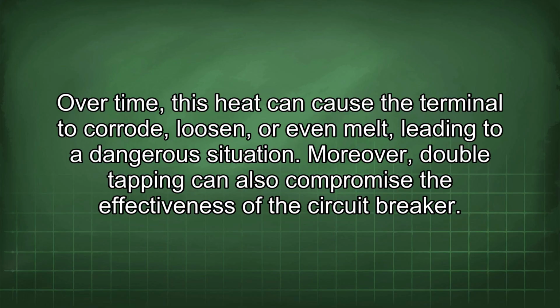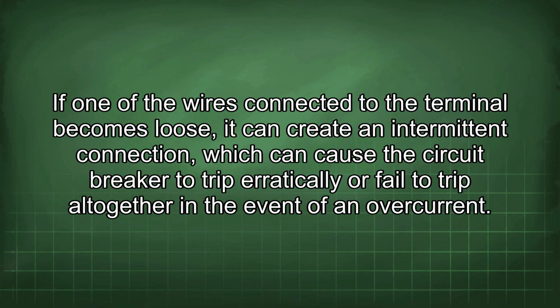Moreover, double tapping can also compromise the effectiveness of the circuit breaker. If one of the wires connected to the terminal becomes loose, it can create an intermittent connection, which can cause the circuit breaker to trip erratically or fail to trip altogether in the event of an overcurrent.